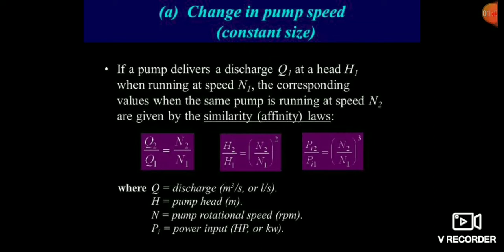Q2 by Q1 is equal to N2 by N1 — if the discharge is double, then the running speed is also double. The second relationship: pressure head is proportional to the square of running speed. If the running speed is double, then the pressure head will become four times because it is squared.